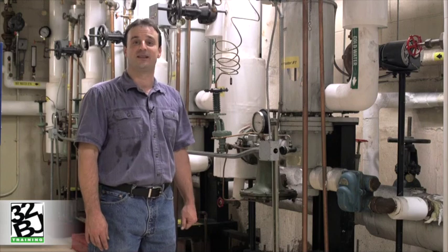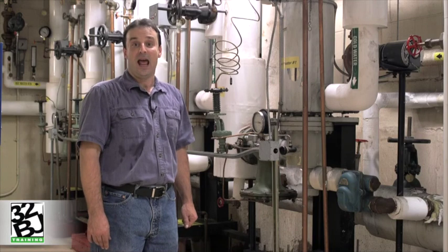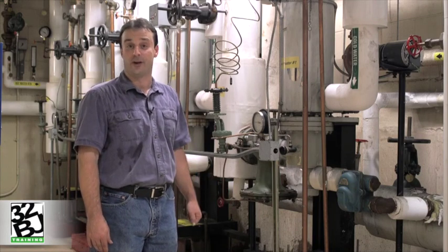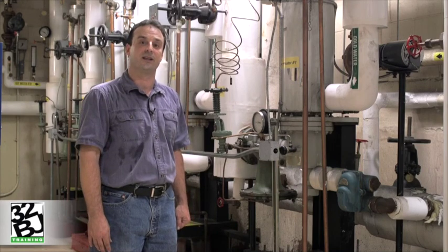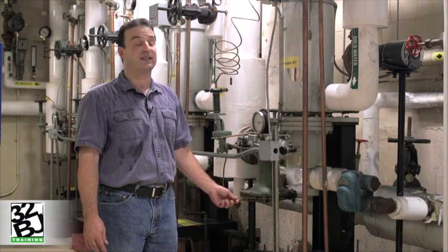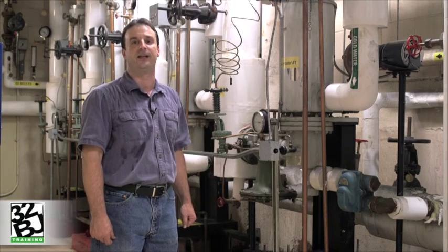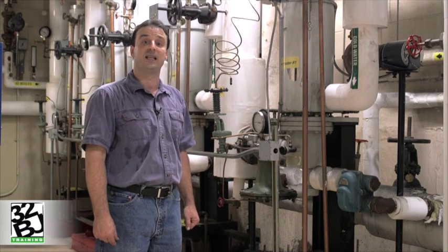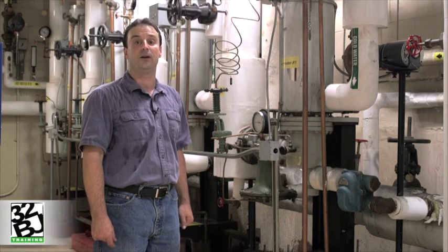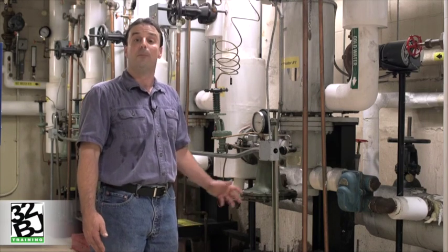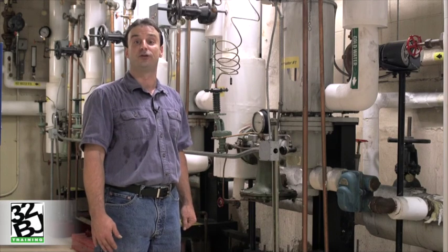Efficiencies surrounding the semi-instantaneous hot water heater vary greatly depending on the availability and the production of the steam required for their use. In buildings using district steam for heating and hot water services, the availability of the steam can be very advantageous in the use of the semi-instantaneous hot water heating system. When producing that steam on site, boilers will need to run 365 days a year, not only to produce heat for the building, but to provide hot water, and the efficiency will vary greatly based on the combustion efficiency of that boiler.